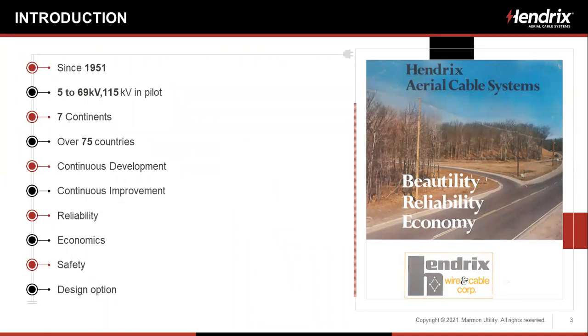And 2 years ago, almost 3 years ago, we went into our 115 kV pilot. We're on all 7 continents. We've got over 75 countries installed. We've got continuous development, continuous improvement, and we're installed for reliability, economics, safety. And as I always say, spacer cable may not be for everywhere. It's a design option, and we've got to keep that in mind.